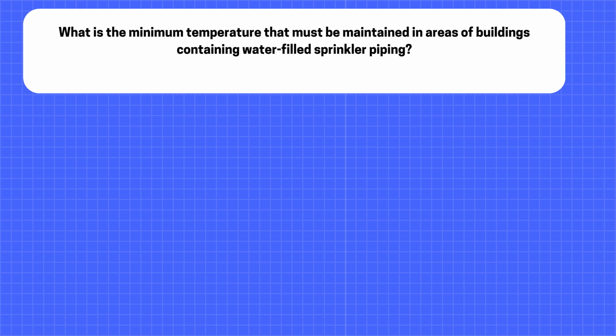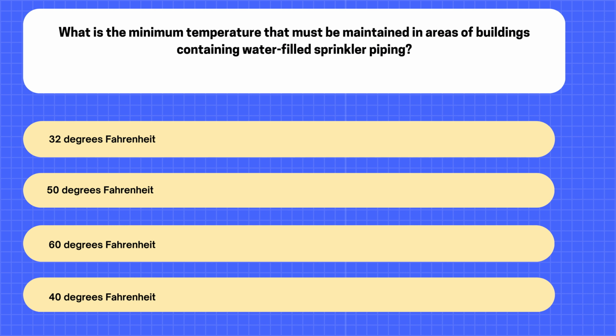What is the minimum temperature that must be maintained in areas of buildings containing water-filled sprinkler piping? A. 32 degrees Fahrenheit. B. 50 degrees Fahrenheit. C. 60 degrees Fahrenheit. D. 40 degrees Fahrenheit.